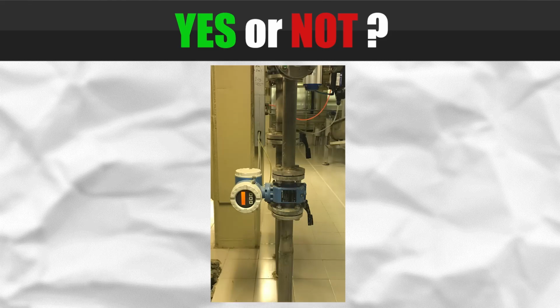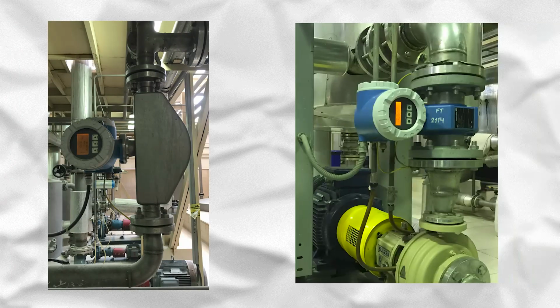Perhaps you have just come up with the question of whether it is possible to install a flow meter on a vertical pipe or not. I can say yes, as long as the direction of flow has been checked. For liquid, the flow direction must be upward. On the other hand, for gas services, it must be downward. We consider the flow direction in this way to keep the pipe full. Thus, the measuring is carried out more accurately.